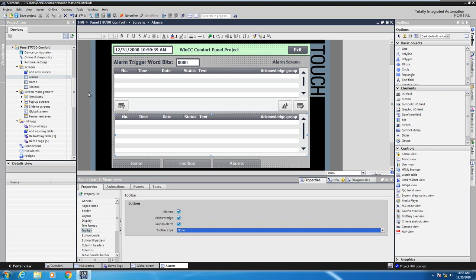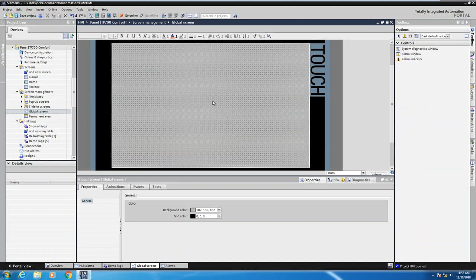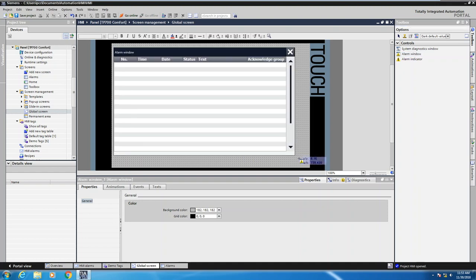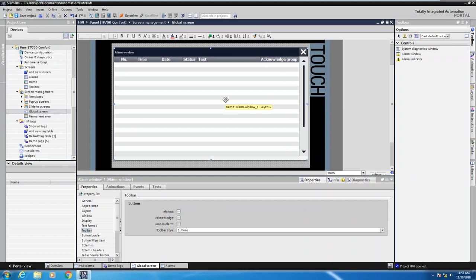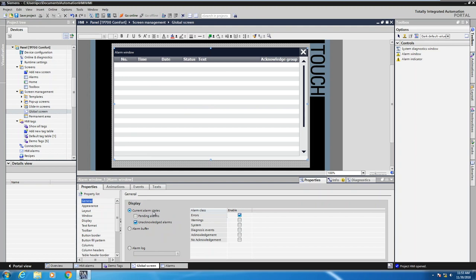Now I'm going to move over to the screen management area, specifically the Global Screen. I'll open up the global screen — this is used to display a pop-up window on every screen in your application as alarm conditions occur. When I open the global screen, my toolbox changes and I just have access to Controls. I'll select an Alarm Window and draw it out onto the screen — this will be a pop-up window, which is different from an alarm view. Looking at the general properties of the alarm window, it is set to Current Alarm States and Unacknowledged Alarms, so only newly triggered alarms will show up in this pop-up. The default filter is set to display only the Error condition, so warnings will not show up in this pop-up window.